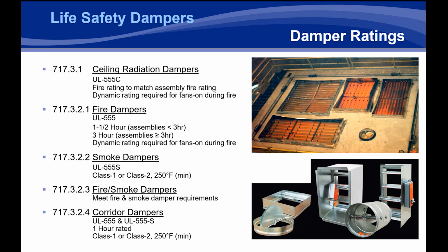What UL is also planning to do with that is to not only certify dynamically rated ceiling radiation dampers, but to certify floor ceiling assemblies as dynamically rated or statically rated. Right now, the majority of floor ceiling assemblies in the UL fire resistance directory are statically rated. So they've never been evaluated to have the fans on during that fire. UL stance right now is all of those assemblies would have to be fire tested with a fan running to get a dynamic rating. That would also apply to the damper. So you can't test the damper separately for a dynamic certification at this point. You have to develop an entire floor ceiling assembly.